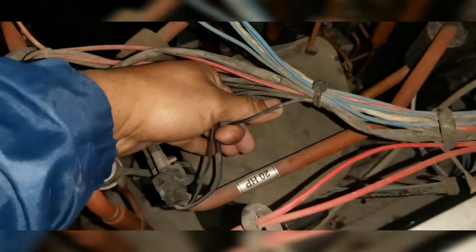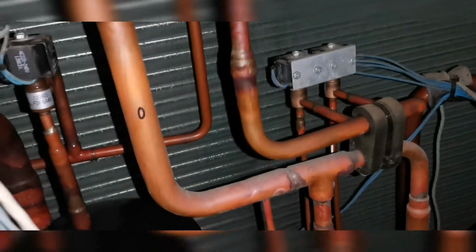Here's our compressor suction side. Discharge right here, as you can see, it's a 20 horsepower system, and this right here is our vapor injection. So yeah, we've got our two EVI solenoid valves which run on this line. So this is a cool vapor line, as you can see over here from our suction accumulator. We've got another solenoid valve, but really it happens down here. So that right there is our intercooler, and we've got an expansion valve on that as well.